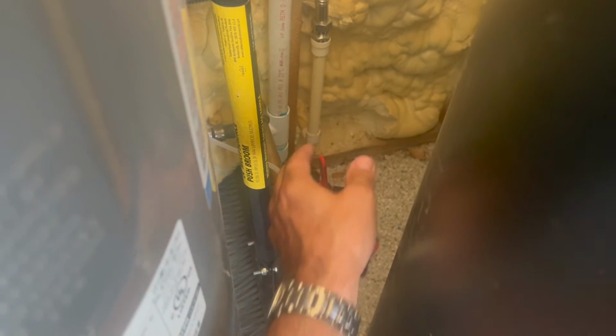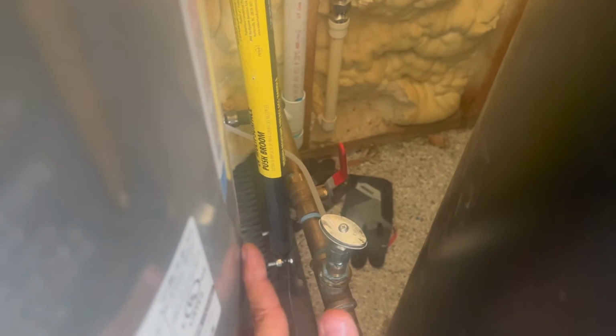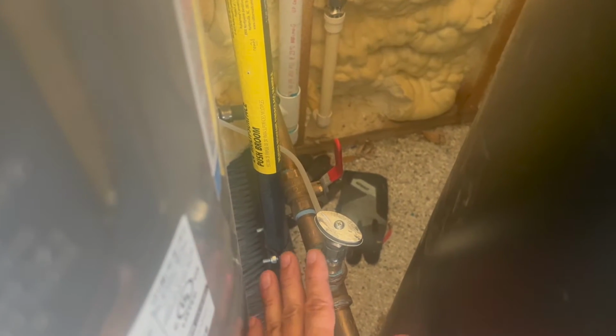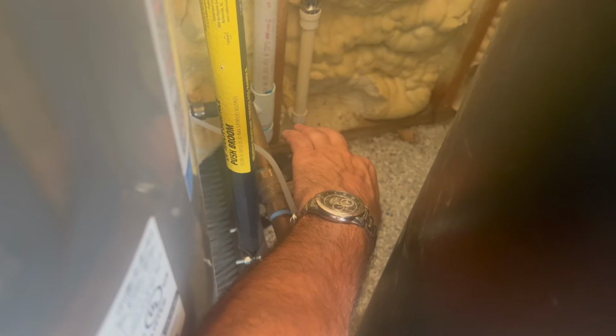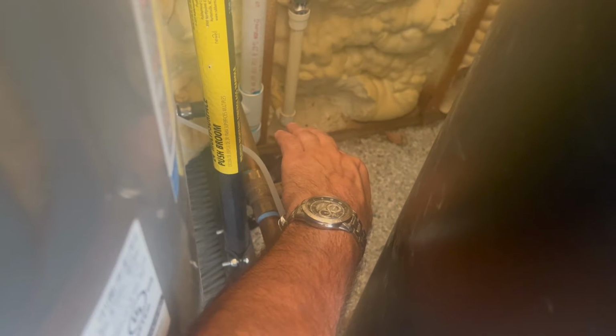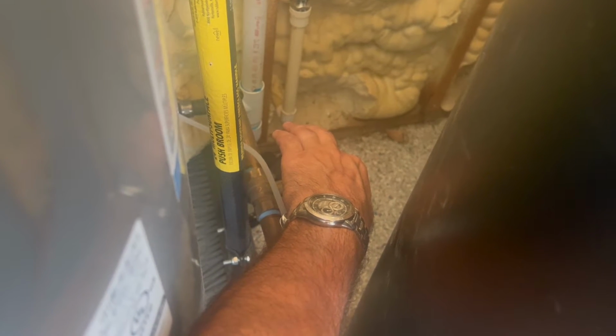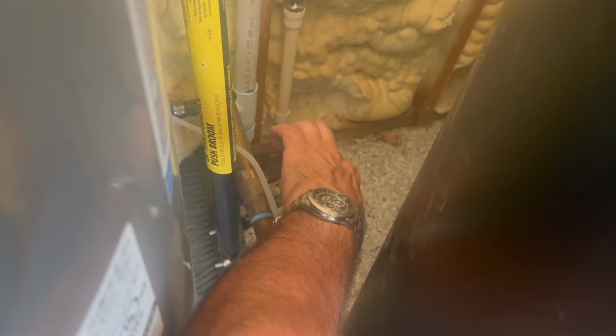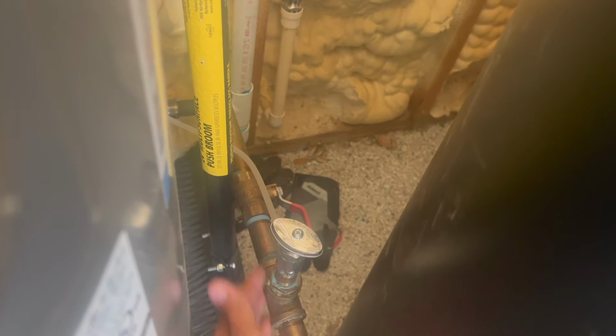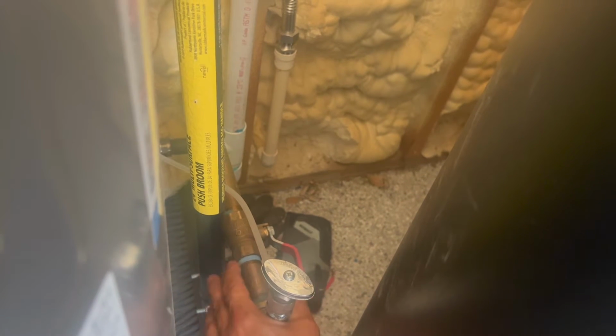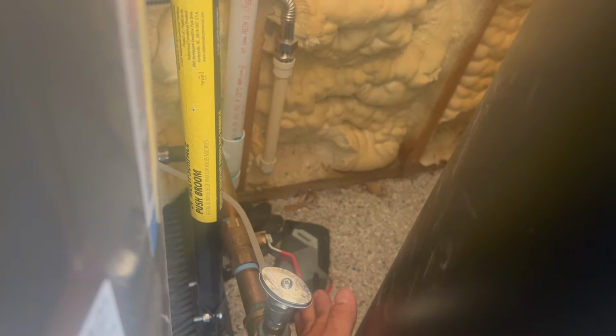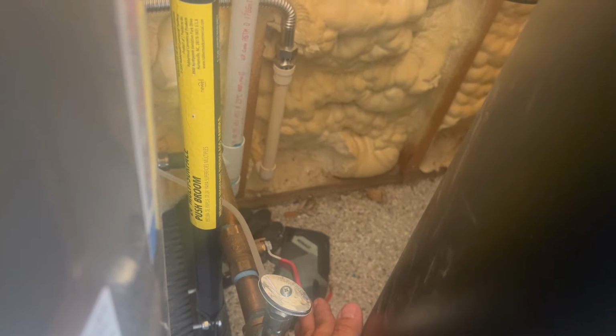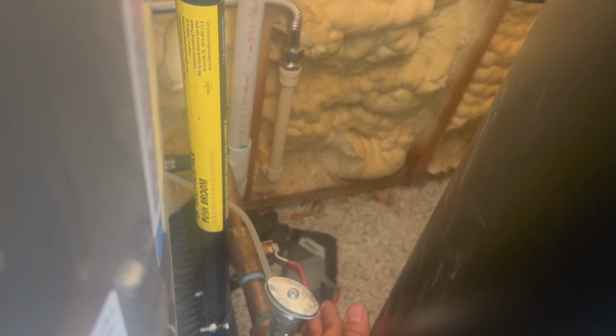Now here's something you want to listen for. This water heater is off. There's no known leaks on this system. When I turn this valve back on, and if I was testing for a leak, I would wait a little bit longer. But for time savings, we're just going to do it now. I turn it back on. I did not hear any water movement, meaning there wasn't any water loss after that. If there's a leak in the system, you'll hear the noise pressurizing the system back up when you turn this valve back on. That's a good indication that water is running out somewhere, and you'll need to locate that leak.